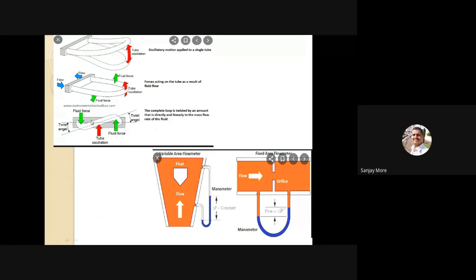See the twist angle. Here the axis is the twist angle. This is the twist angle. It means when the flow reaches high pressure, this tube will oscillate, and you have to measure this oscillation. The complete loop is twisted by an amount that is directly and linearly related to the mass flow rate of the fluid. And here, variable area flow meter and fixed area flow meter.